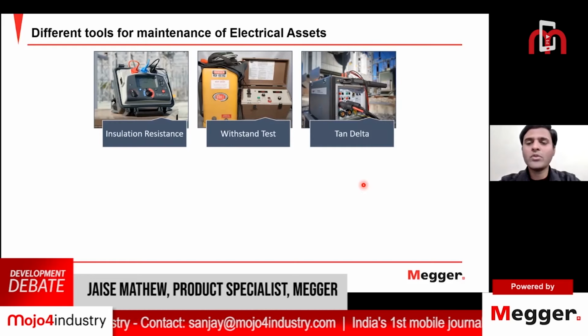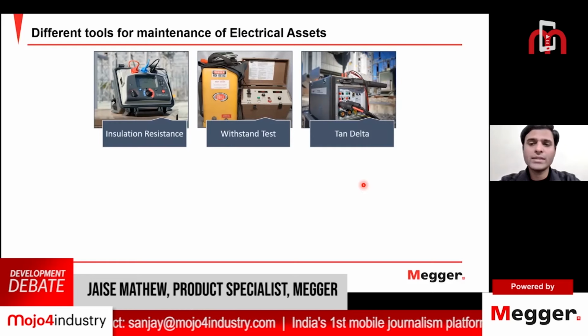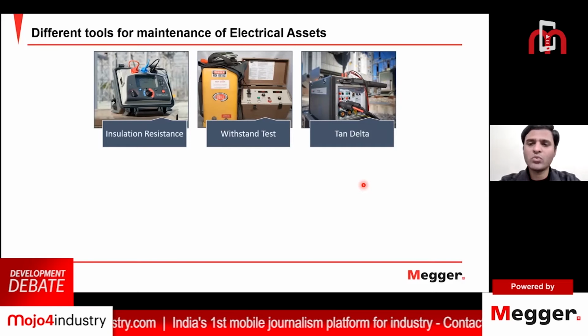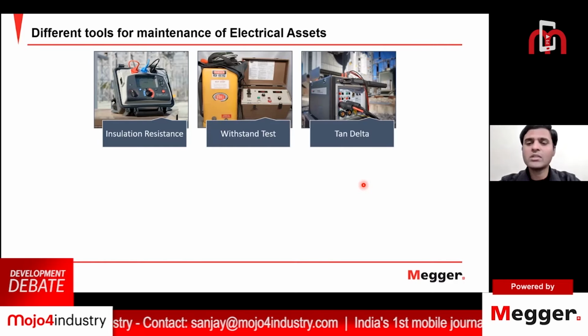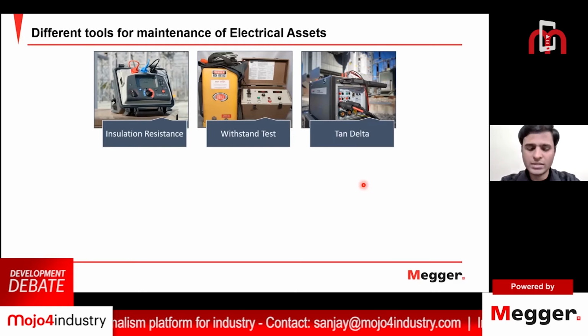That means many of our electrical assets work on AC conditions. So tan delta measurement is carried out with an AC test voltage, and the values of the tan delta measurement will help us understand whether your electrical asset has deteriorated or not. For example, in a transformer, if there is some moisturization or any deterioration, you can do more investigation on that particular asset where you have a high tan delta value above the threshold limits, which are set by the different standards for different electrical assets.